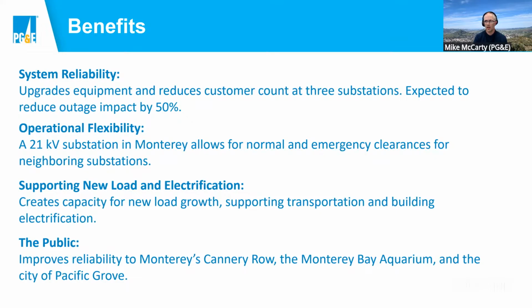Now, that doesn't mean that everywhere in the distribution system has that spare capacity, because a lot of that is location-specific and we'd need to build or upgrade the line going to that location. But at least the substation itself has the ability to take on that new load.